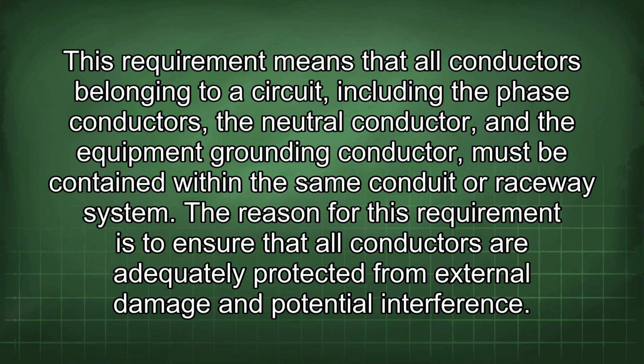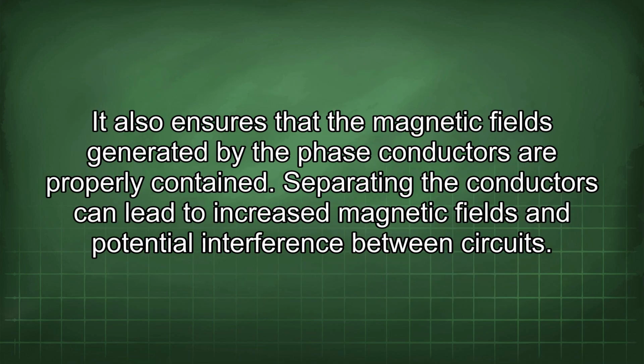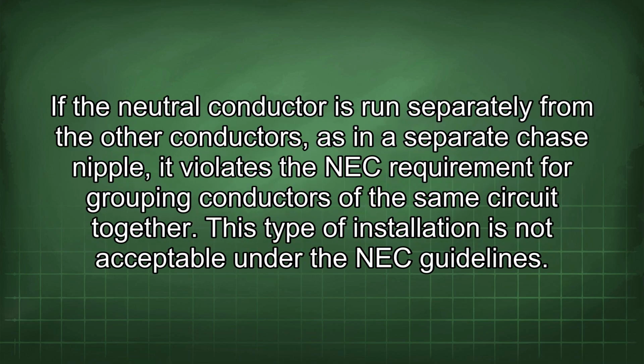The reason for this requirement is to ensure that all conductors are adequately protected from external damage and potential interference. It also ensures that the magnetic fields generated by the phase conductors are properly contained. Separating the conductors can lead to increased magnetic fields and potential interference between circuits. If the neutral conductor is run separately from the other conductors, as in a separate chase nipple, it violates the NEC requirement for grouping conductors of the same circuit together. This type of installation is not acceptable under the NEC guidelines.